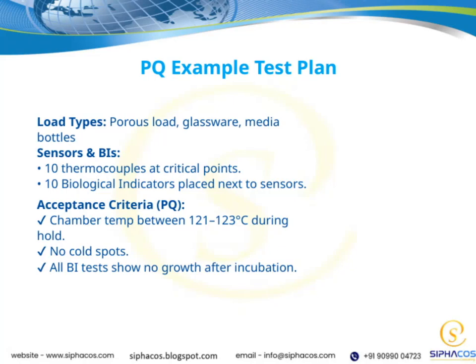Let's take a closer look at the PQ example test plan. First, we have the load types, which include porous loads, glassware, and media bottles. These are representative items that we typically sterilize, and it's important to test these to ensure our sterilization process is effective across different materials. Next, we have the sensors and biological indicators. We've placed 10 thermocouples at critical points throughout the chamber to monitor temperature accurately during the cycle. Additionally, there are 10 biological indicators positioned right next to those sensors, providing a direct measure of sterilization efficacy.